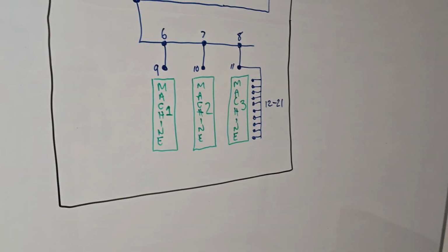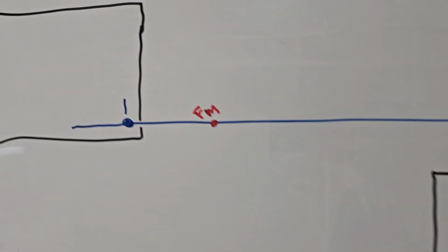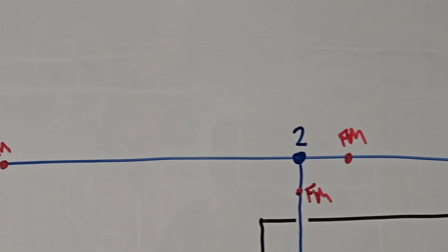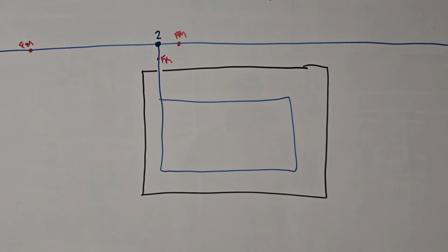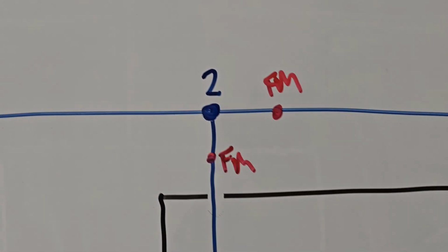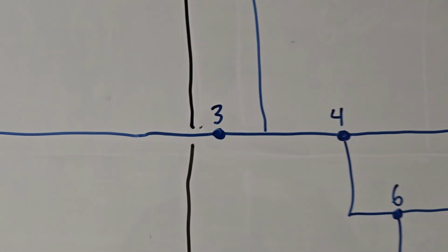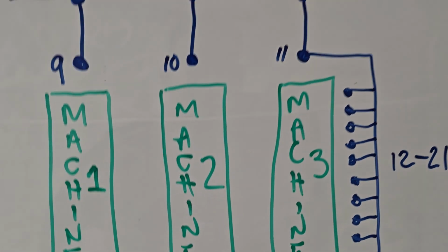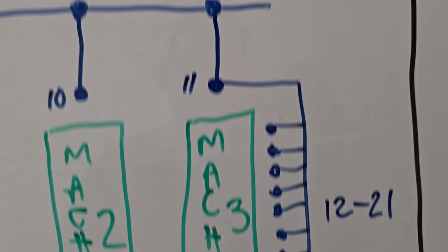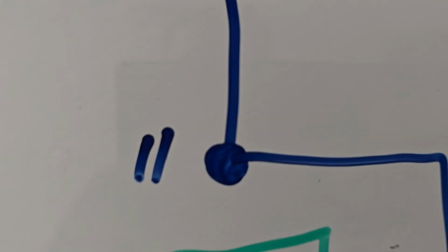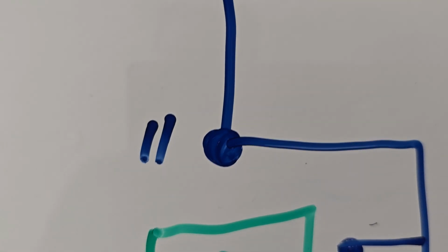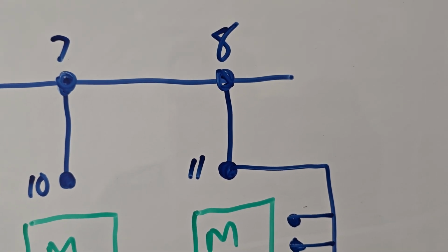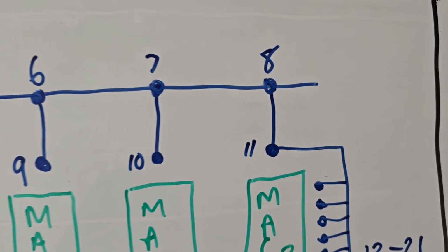So let's look here. The customer system, they have a compressor room here. The piping leaves the compressor room and comes down to the first building here. This pipe extends to a second building there, and at this specific machine, labeled machine 3, at point 11, they are getting low pressure alarms. They're intermittent. Sometimes they can last upwards of 12 minutes, sometimes they're as short as 10 seconds.